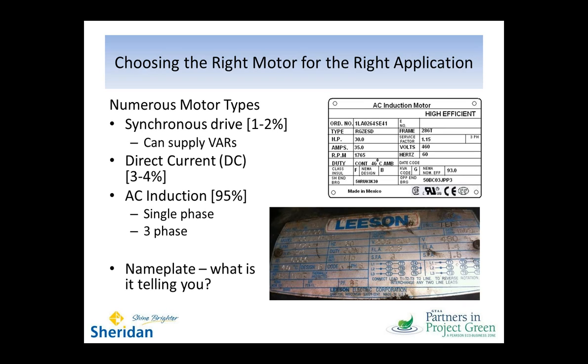Direct current drives are sort of the next most common, about 3 to 4% of install base, maybe even 3 to 5%. They're historically used for things like precision speed control, applications requiring high torque or rapid starting and stopping, servo motors, things that require accurate positioning. But they historically have been considered high maintenance, particularly the ones that had brushes, because the brushes have to be replaced on a regular basis, as do slip rings. They have to be disassembled and reassembled. And these days, you might effectively replace the functions of a DC motor drive with an AC variable speed drive, which I'll get to in a little while.